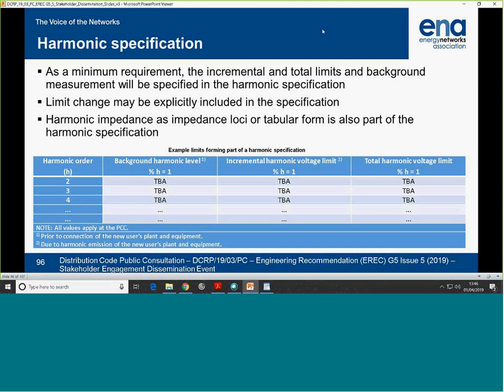In addition to this, the customer, in order to check compliance against these limits, needs the impedance loci at the PCC. In order to get this table, you need the impedance profile, the harmonic impedance of the PCC. Then the user has got all the information to check compliance.